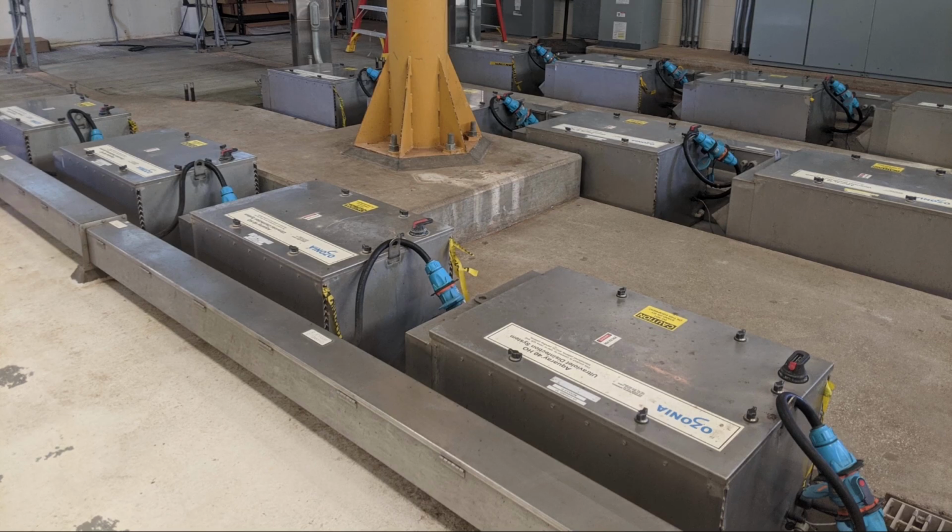The last step in the process is disinfection. This plant uses ultraviolet C or UVC light. As you can see, we have 3 rows of 4 units, with each unit having 40 165 watt lamps, so that's 79,200 watts of UV lamps in total, not even including ballast losses. In the background, you can see the cabinets that supply the 480 volts these run on.